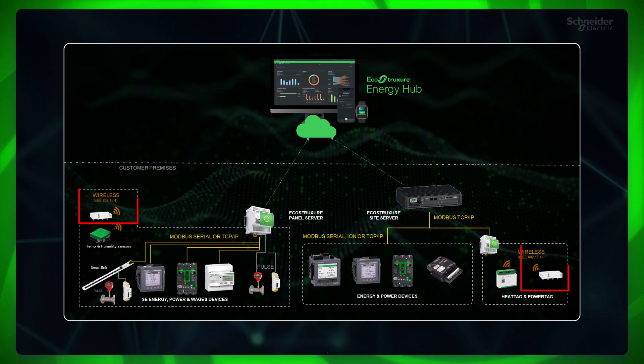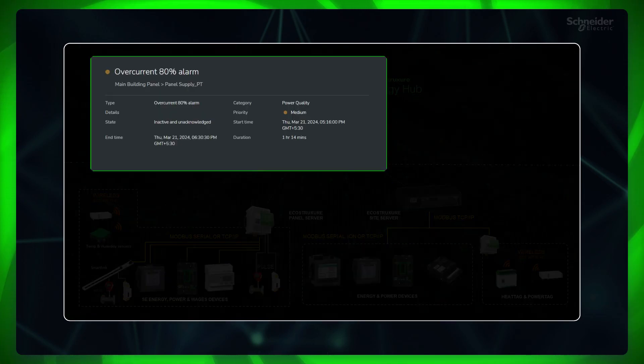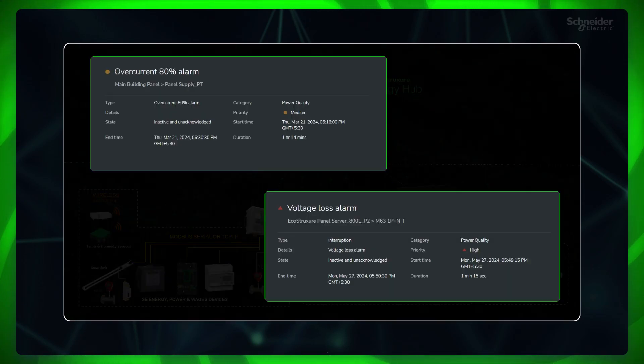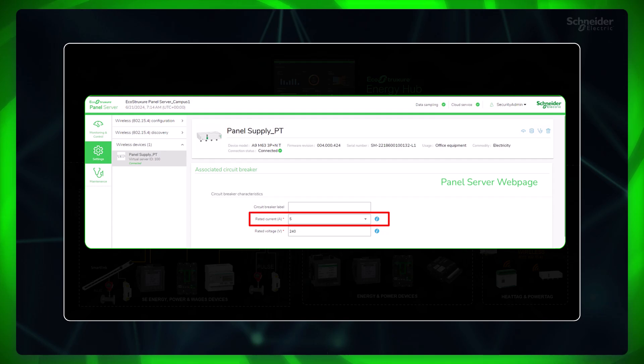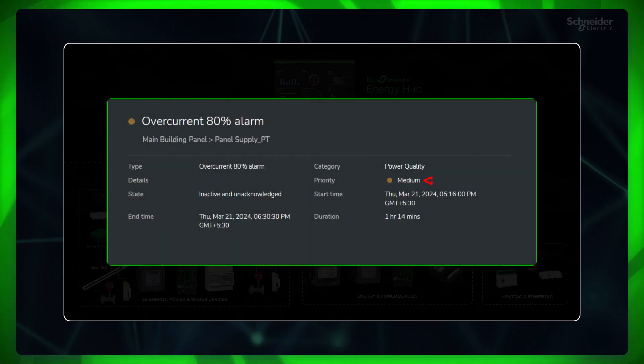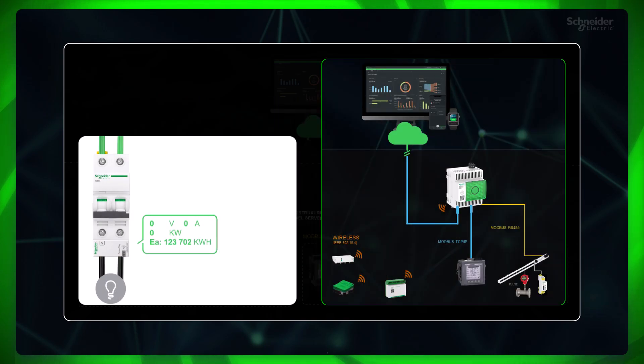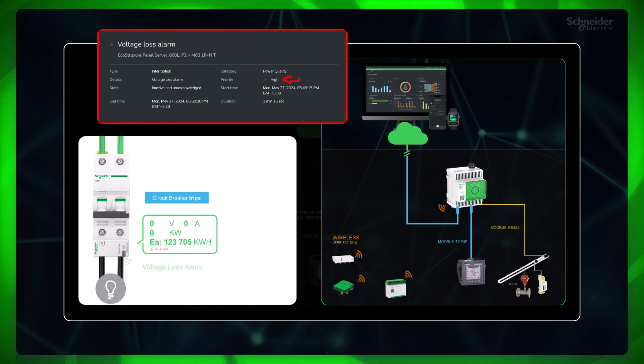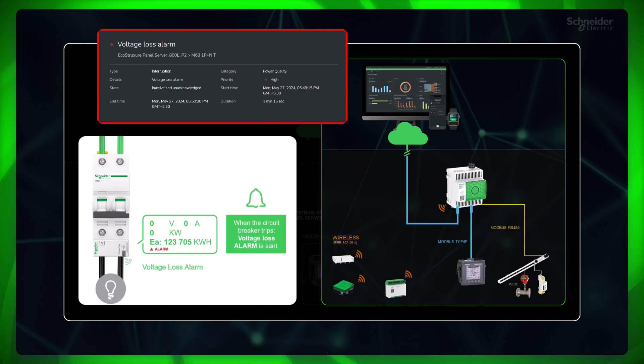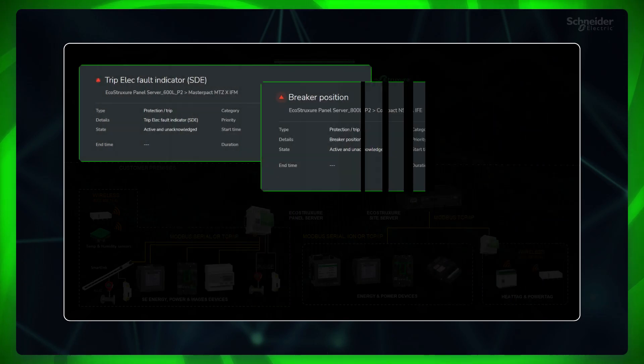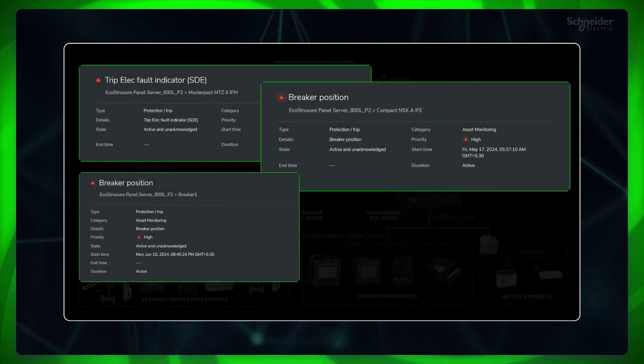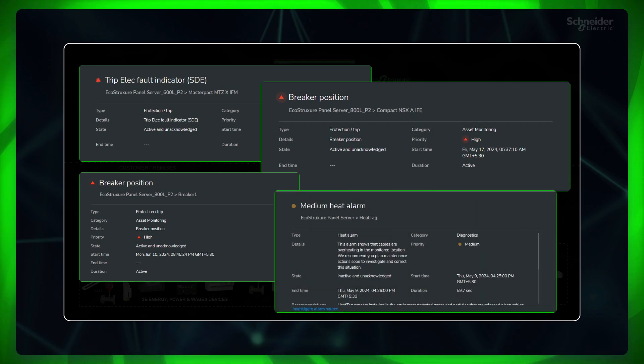Let's see a few device alarms. If a PowerTag Energy sensor with panel server is at the site, it gives overcurrent 80% and voltage loss alarms, which come in the category of power quality. When the current value exceeds 80% of the nominal current of the sensor, an overcurrent 80% alarm is generated with medium priority. When the voltage becomes zero, the voltage loss alarm is generated with high priority. If the PowerTag Energy sensor is installed at the load side, voltage loss means a possible breaker trip. Breaker alarms, ACTI9 auxiliary status alarms through smart link, and heat tag alarms are some additional examples of device alarms.